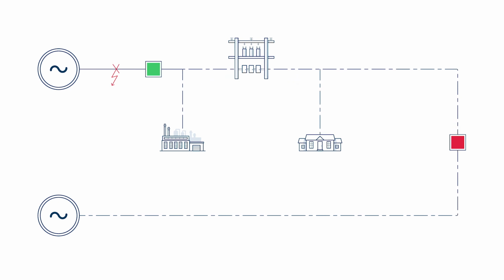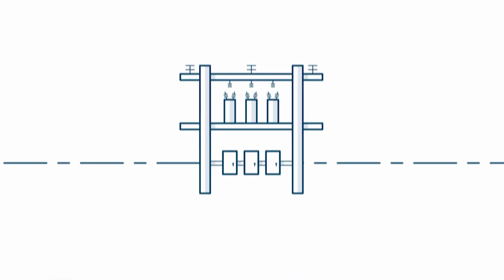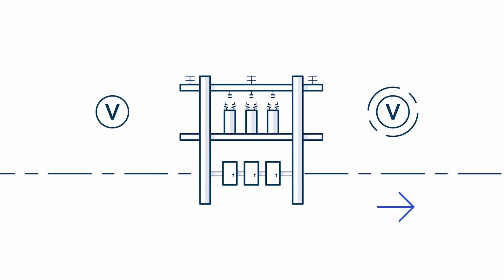This is important because a voltage regulator can't change the voltage in the part of the circuit that sits between it and a substation that delivers bulk power. For our purposes, we'll call these traditional substation sources stiff sources. If we attempt to increase voltage on the side that has a stiff power source, we achieve nothing. And on the other side, we actually reduce voltage.